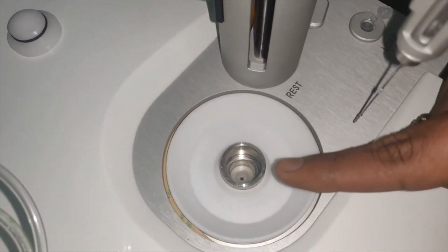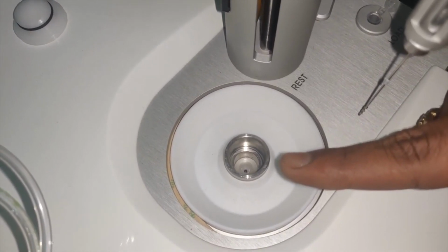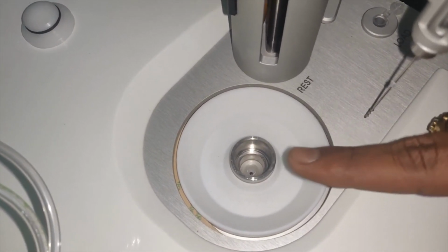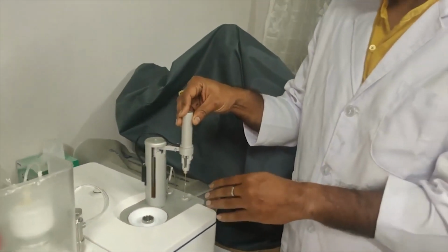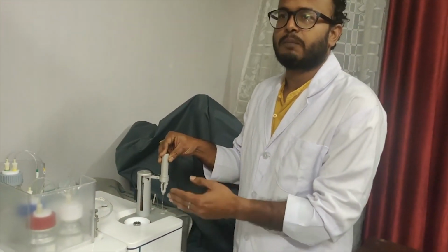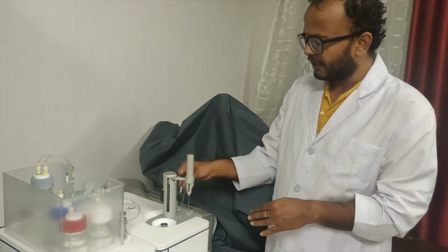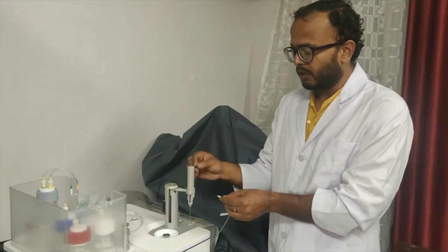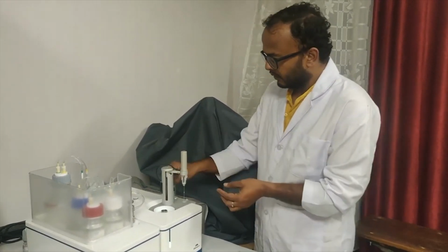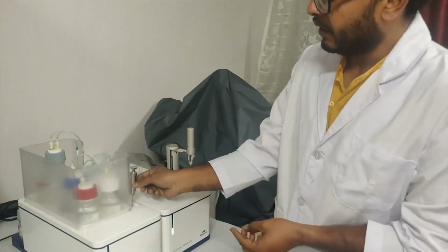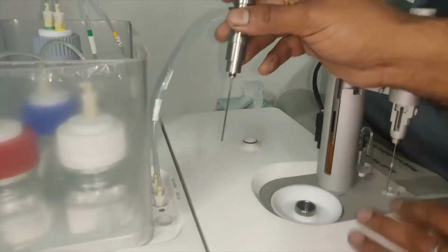That is constantly filled with 280 microliter of water, and it need not be changed every time, but around once in 2 weeks or in a month. Now this is the syringe in which we generally load the entity of higher concentration, or in a protein-ligand interaction we can say we put the ligand into this syringe. This is the fill port adapter which is required during cleaning or during loading of the ligand into the syringe. And this is called the cell cleaning tool, which is used during the cleaning of the cell.